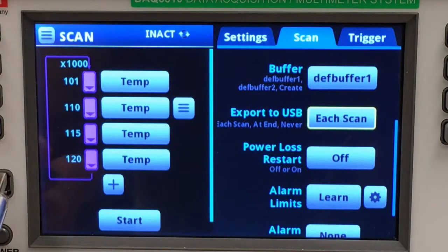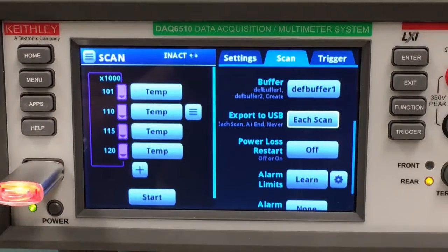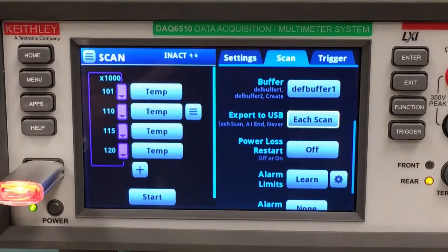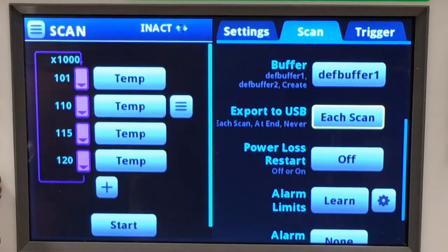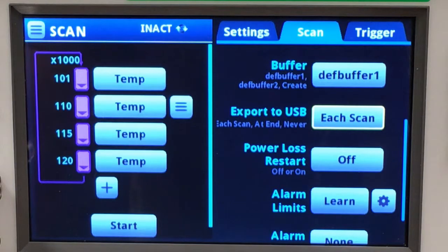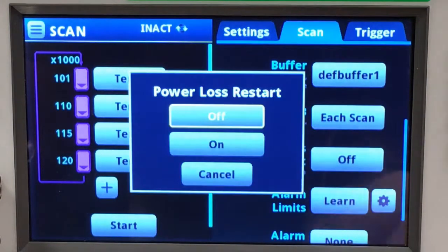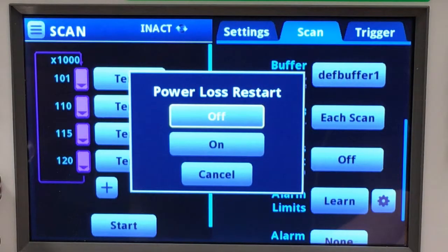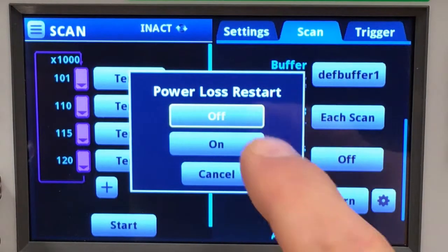I'll take my USB drive and place it into the front of the DAQ 6510. And should the power go off sometime early in that 16-minute scan, I want it to restart from the very beginning without my intervention, so I will turn power loss restart on.